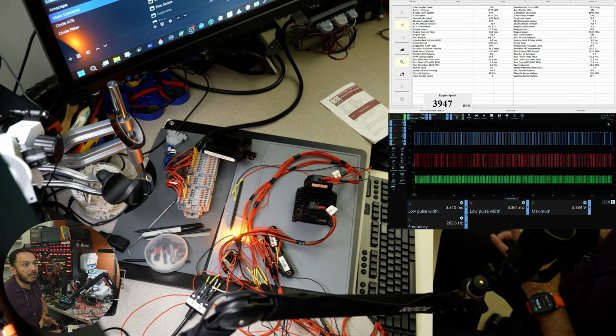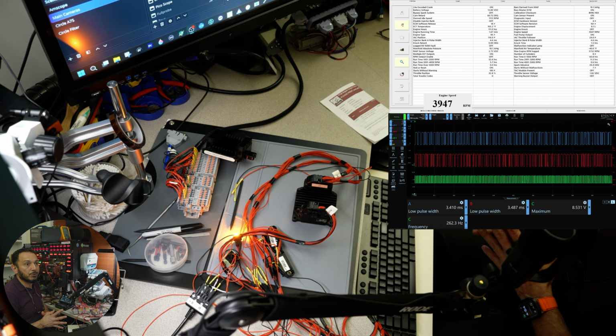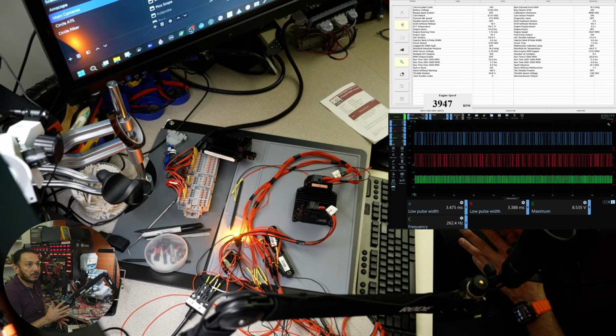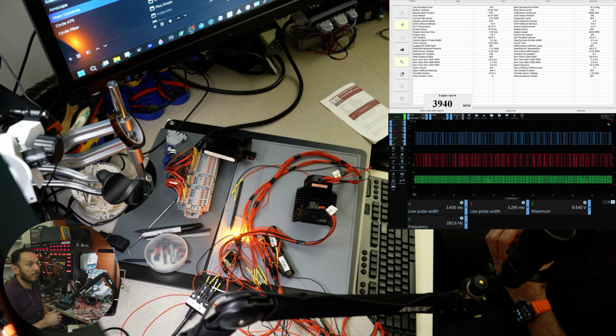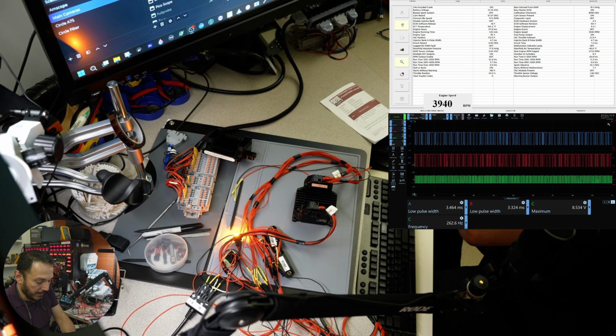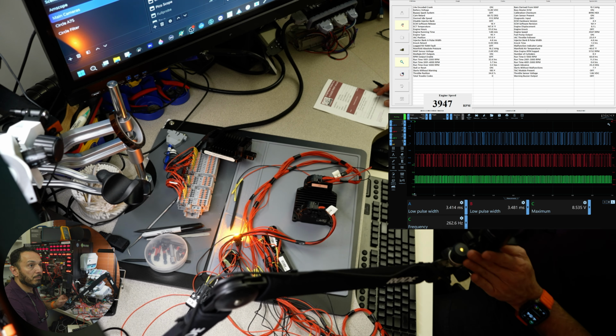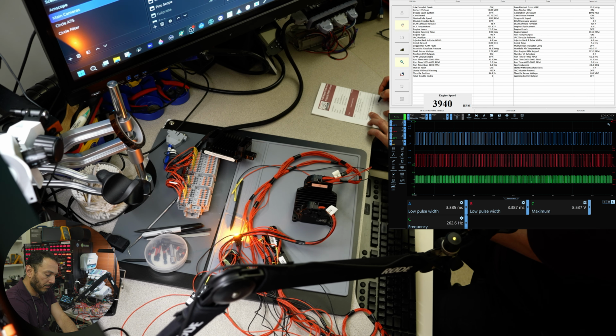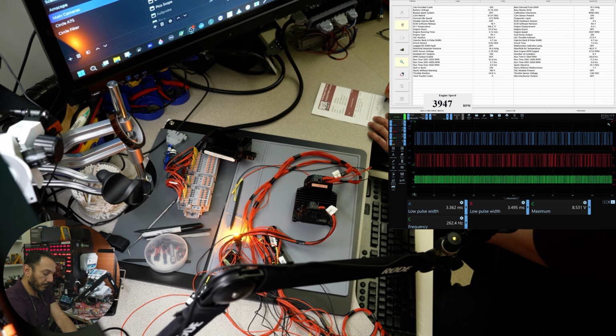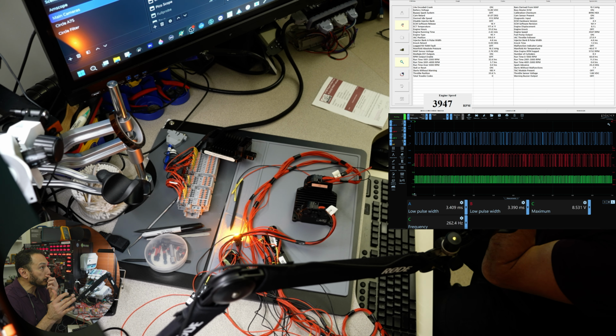The manifold pressure, I'm going to leave as is. So we have 4.5. The only thing that I'm going to change, and I'm going to leave it to connect Randy's, is the RPM. So we got 3,940. The hertz, and this is very important, I'm going to write that down here so we can compare. The voltage is staying at 8.5 volts. And this is the tach signal. And the hertz is now 262.3 for 3,940 to 47, right? So plus or minus 7. Actually, it's plus because it doesn't go less. So it's plus 7 because sometimes it's in 40, sometimes it's in 47.